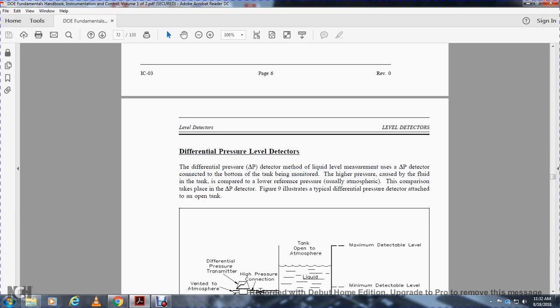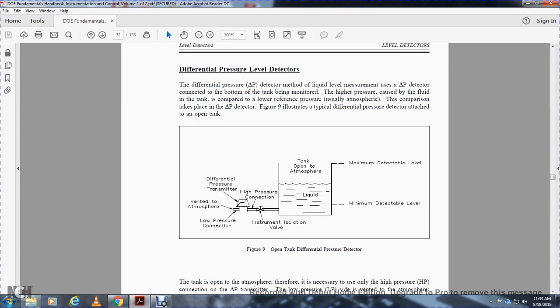Differential pressure level detector. In the differential pressure detector method, the liquid level is measured by monitoring the pressure at the bottom of the tank. The high pressure from the fluid within the tank is compared to a low reference pressure, usually atmospheric. The tank is fitted with the differential pressure detector. Figure 9 illustrates the typical differential pressure detector attached to an open tank.